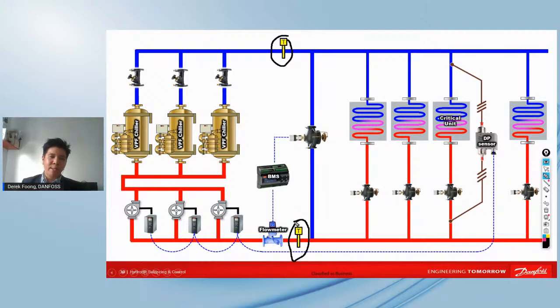The first look on the surface, whether you know if this system is sick or is consuming more energy than required, is that we look at the supply temperature and the return temperature. If the design delta T is about 8 Celsius, and the actual delta is about 3 or 4, then we know there's an opportunity for optimization, right? Because whenever we have a low delta, definitely there'll be problems and inefficiency in the system, whether the coil is clean or not, whether it's over pumping, whether the balancing is out. So that comes to the analytics.